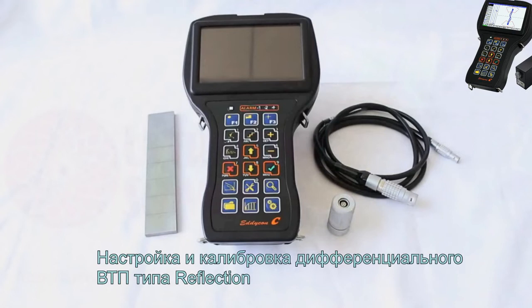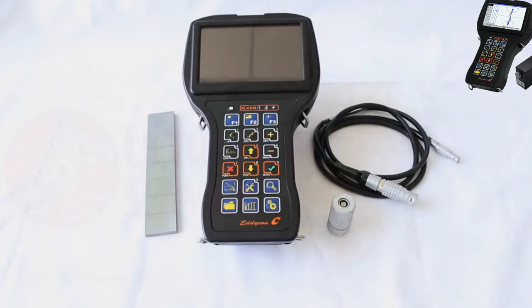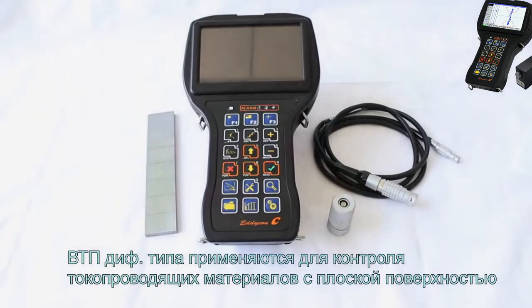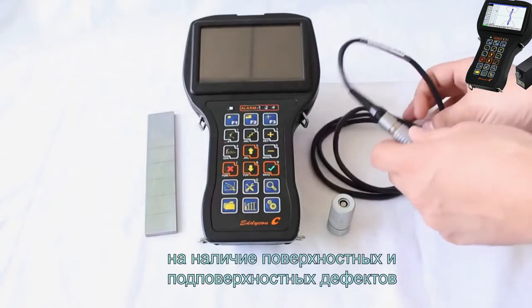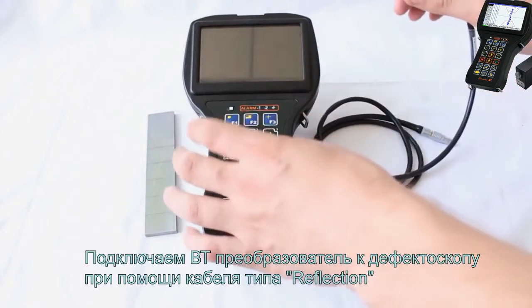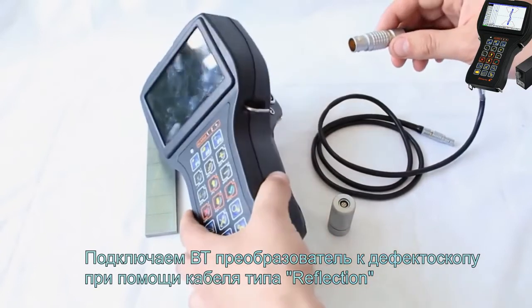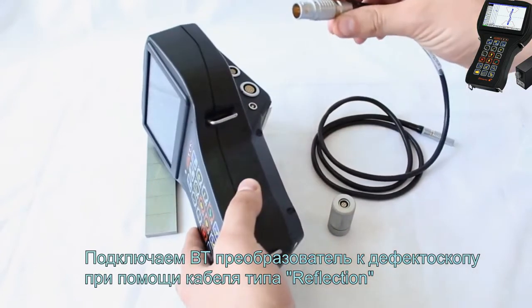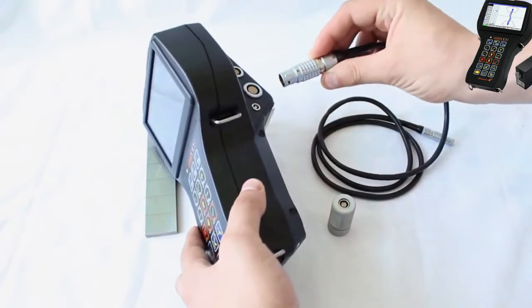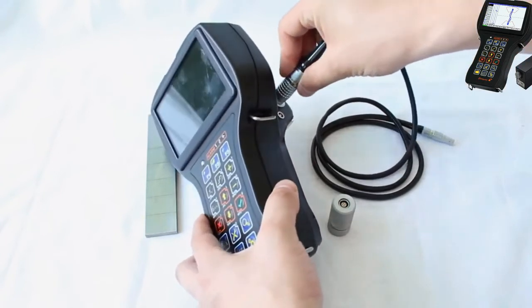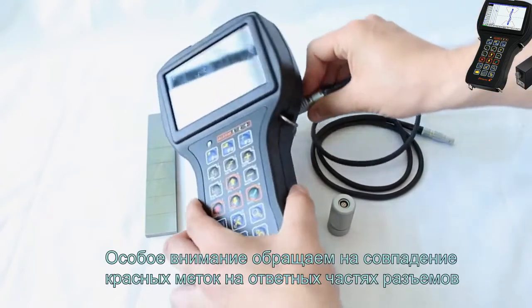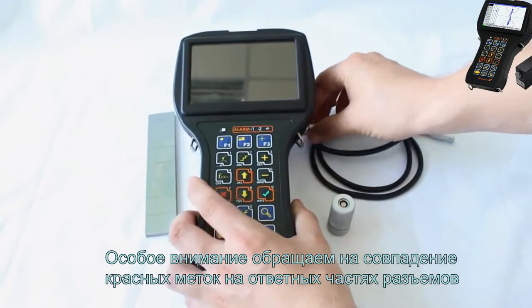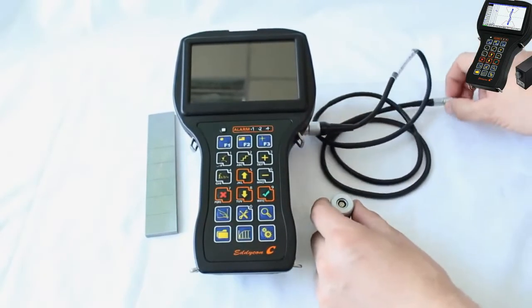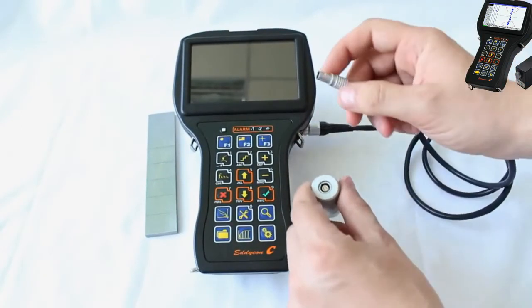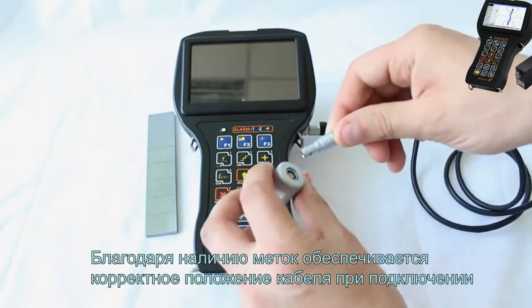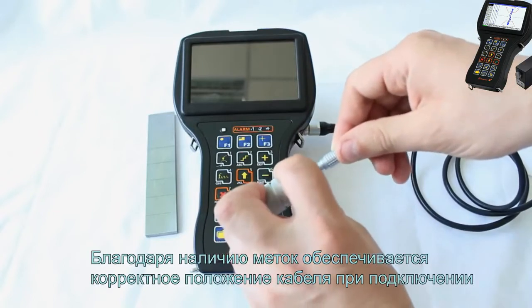Setup and calibration of the differential reflection type EC probe. Differential type probes are used for testing conducting materials with a flat surface for the presence of surface and subsurface defects. Connect the EC probe to the flaw detector using the reflection type cable. Make sure that the red marks on the mating connector parts have been matched. The marks ensure the correct cable position during the connection.